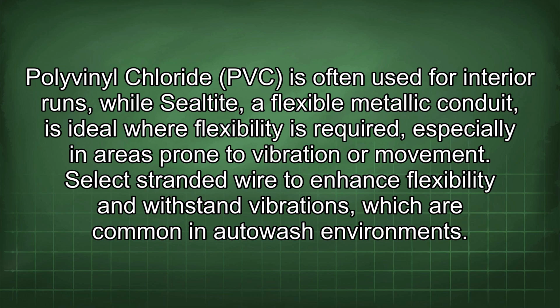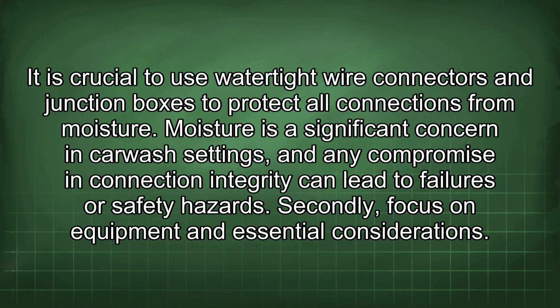Select stranded wire to enhance flexibility and withstand vibrations, which are common in auto wash environments. It is crucial to use watertight wire connectors and junction boxes to protect all connections from moisture. Moisture is a significant concern in car wash settings, and any compromise in connection integrity can lead to failures or safety hazards.